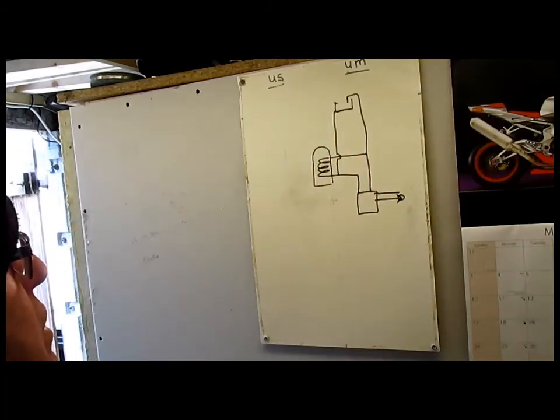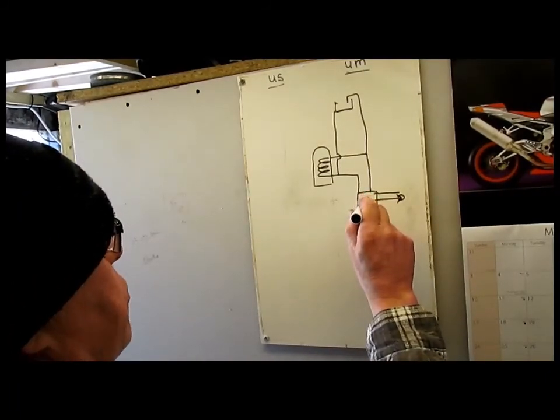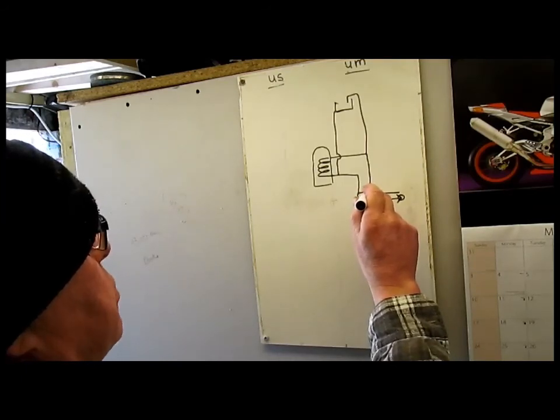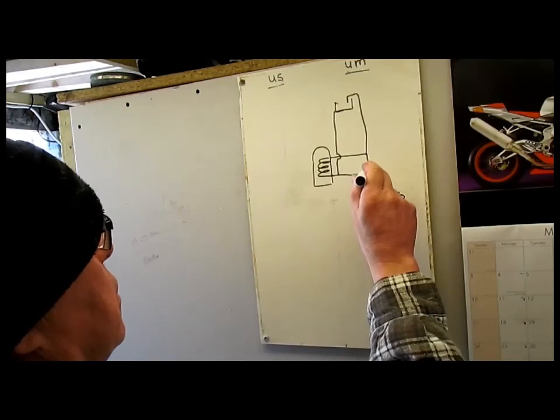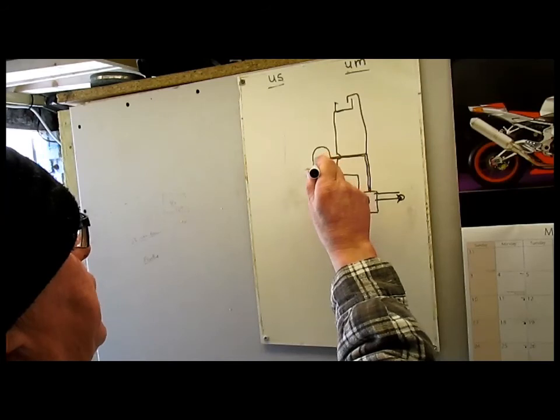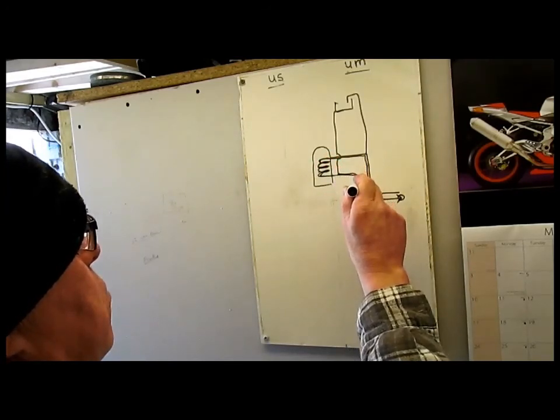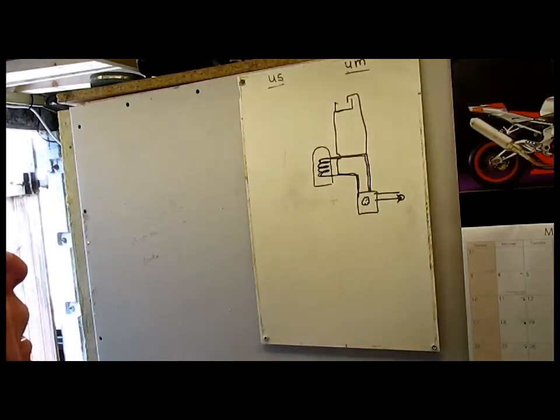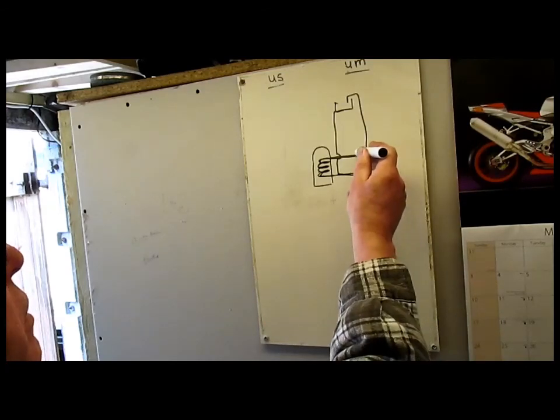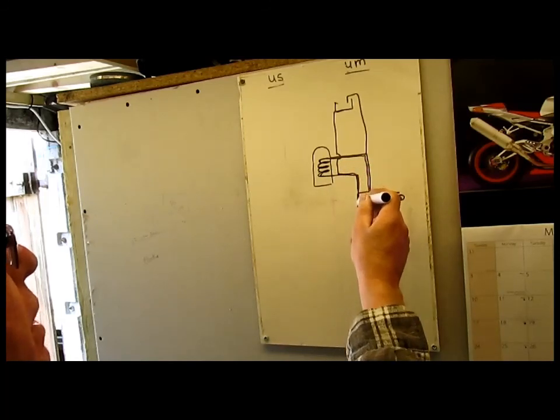And what we're saying it's gravity - it's the water, the movement of the water in here. When the boiler fires up, it heats the water, so the hot water becomes lighter, so it rises, and it goes into the cylinder. And it's giving off its heat, so it becomes cooler and falls back down to the boiler. And it's that motion there of heat making the water lighter so it rises, and then the weight of the cold water falling back down.